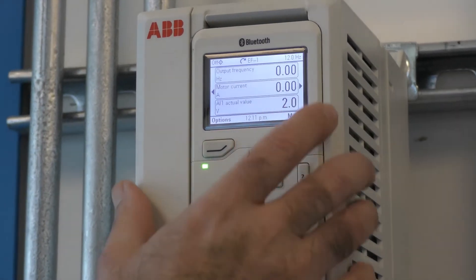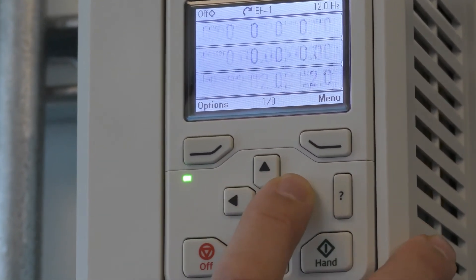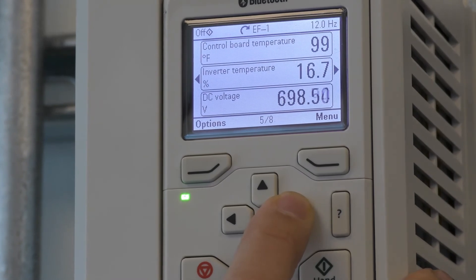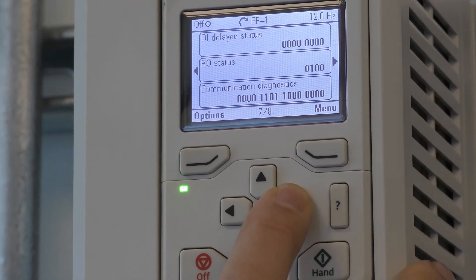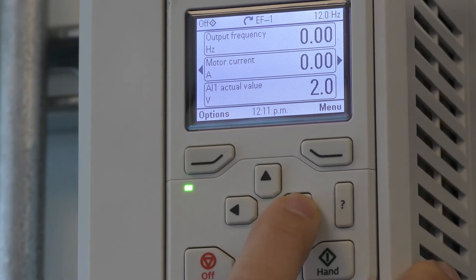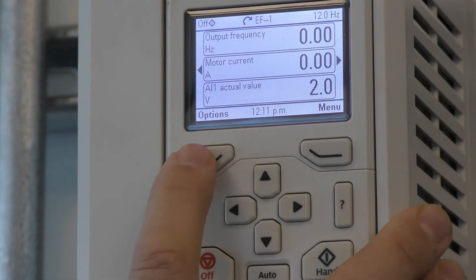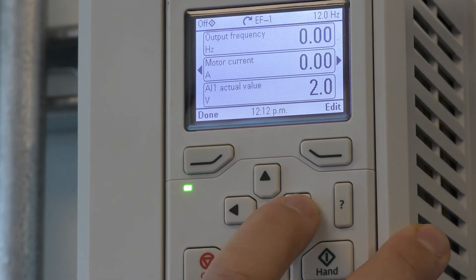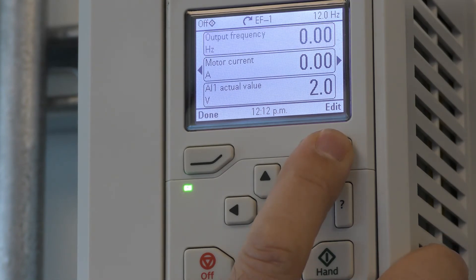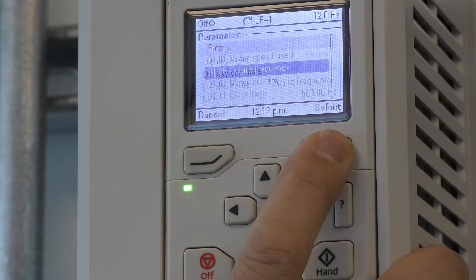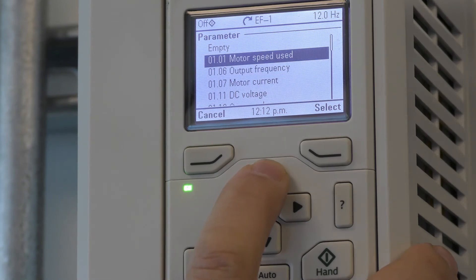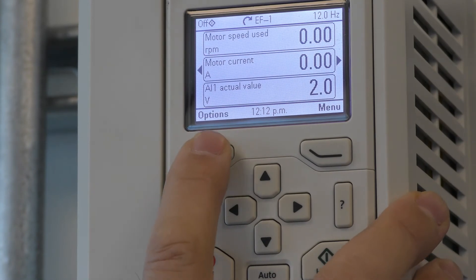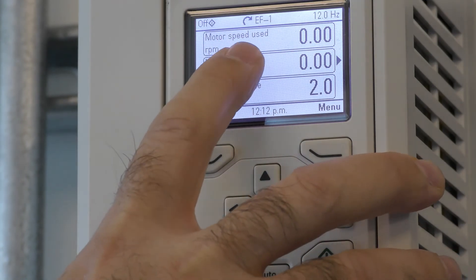Now I'd like to discuss home view. If you hit the right or left arrow you'll come across different signals that you can monitor. These are default from the factory but they can be changed to help diagnose an issue or to see a different view. To change, go to Options, pick Edit Home View, press Edit, press Edit again. I will change it to motor speed used — select, press Done, press Done. Now you'll notice that the motor speed used in RPM is now selected.